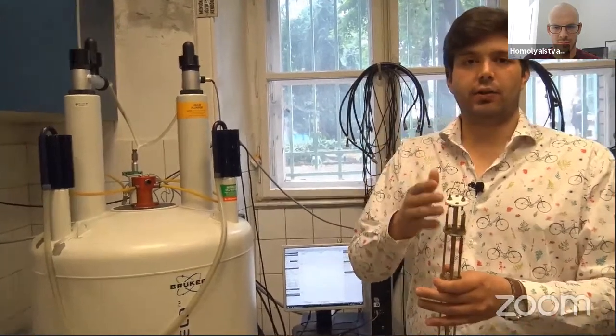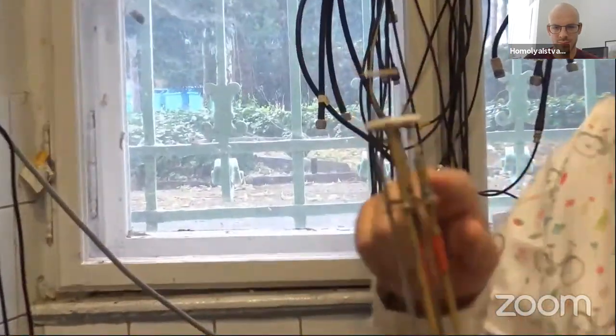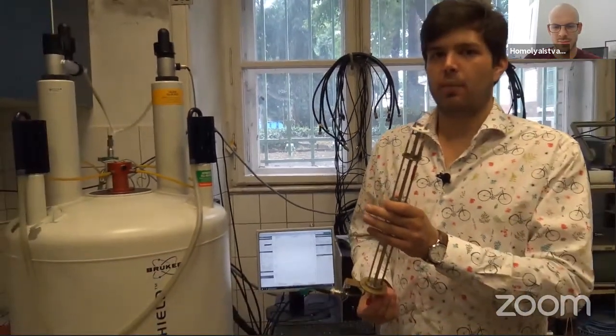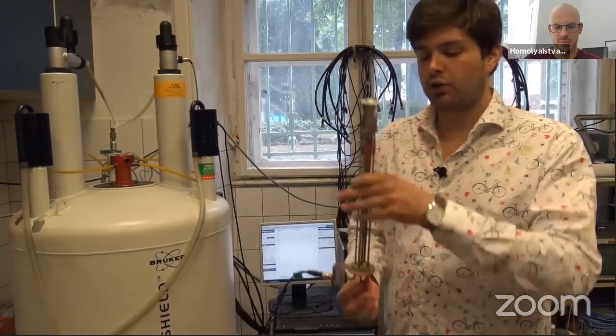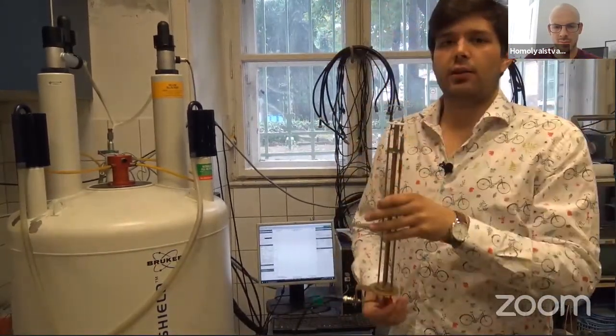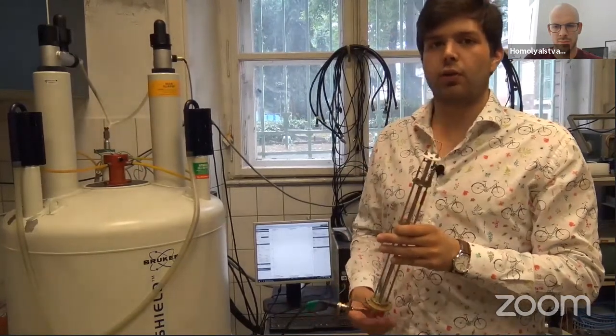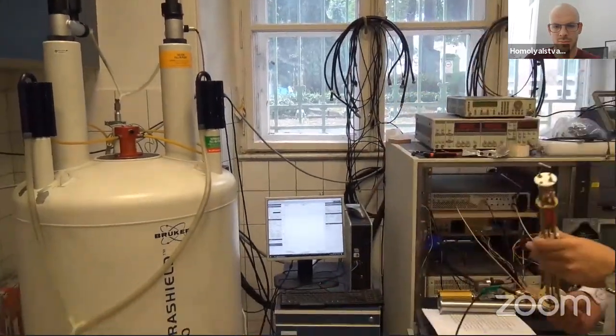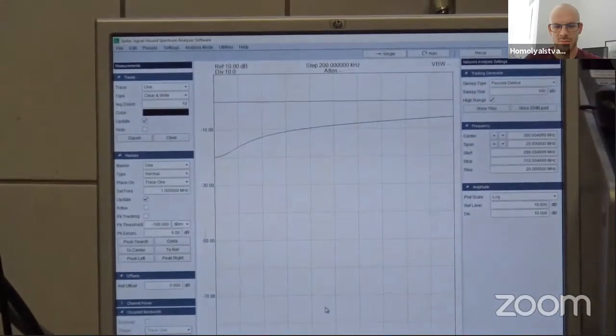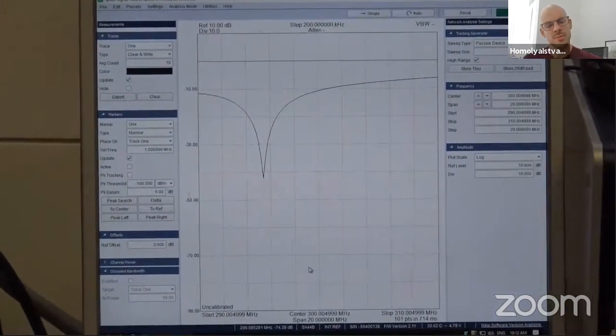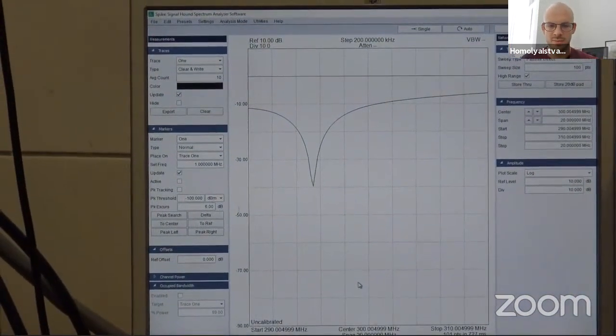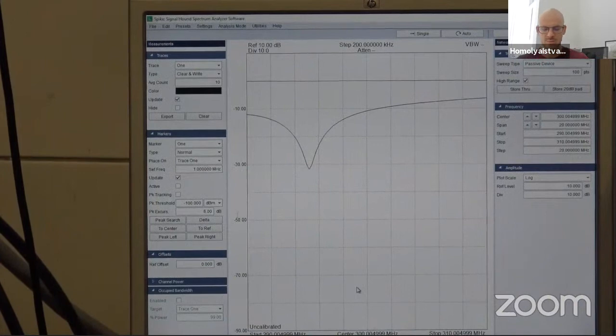When you look at the circuit, you can see beside the solenoid coil two trimming capacitors. These are adjustable capacitors that provide a matching in the frequency. By adjusting with these knobs the capacity of the two capacitors, we can match the Larmor frequency. If you look at the screen, you can see that by turning these knobs, I can tune the frequency and power of the dip. This is important because we also need to match the frequency of the NMR nuclei and achieve a superior dip.